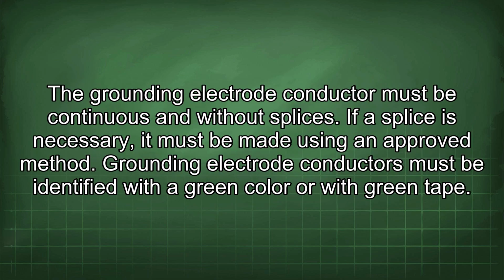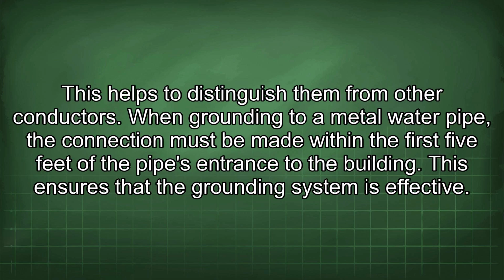The grounding electrode conductor must be continuous and without splices. If a splice is necessary, it must be made using an approved method. Grounding electrode conductors must be identified with a green color or with green tape. This helps to distinguish them from other conductors. When grounding to a metal water pipe, the connection must be made within the first 5 feet of the pipe's entrance to the building. This ensures that the grounding system is effective.